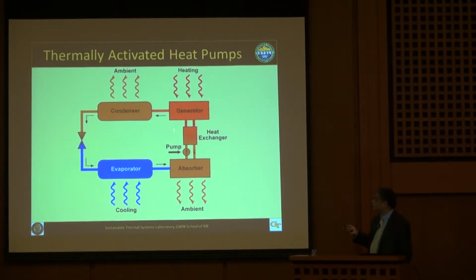So your electrical requirements go down to a very small fraction of the total energy requirements, and there is some recuperation in here. Basically, you are using heat, and using natural fluids, not synthetic fluids, to run this system. But you can see the issue here: you took a compressor, which was one component, and now you replaced it with many other components, so you have to put in more capital cost into the heat exchangers.